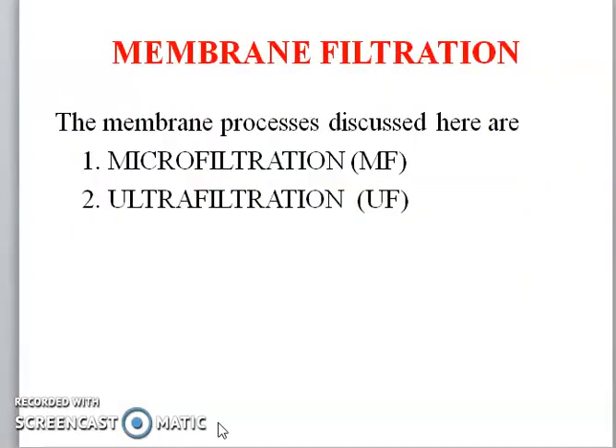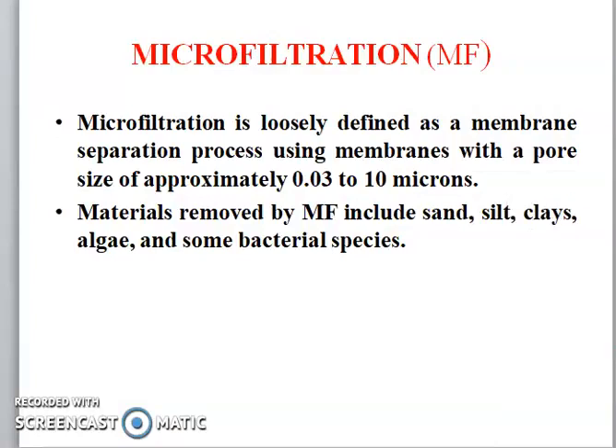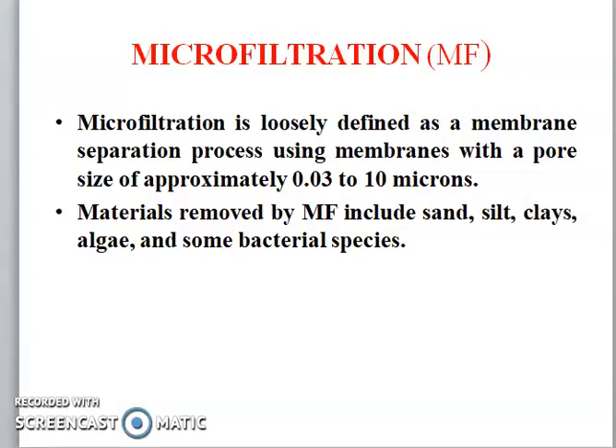Membrane filters are of two types: microfiltration and ultrafiltration. Microfiltration is loosely defined as a membrane separation process using membranes with a pore size of approximately 0.03 to 10 microns. Materials removed by membrane filtration include sand, silt, clay, algae, and some bacterial species.